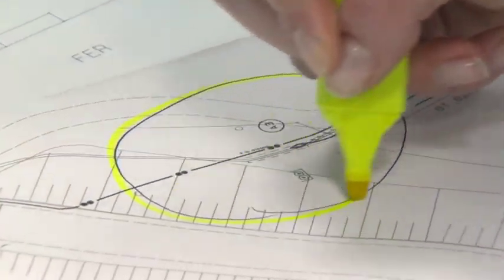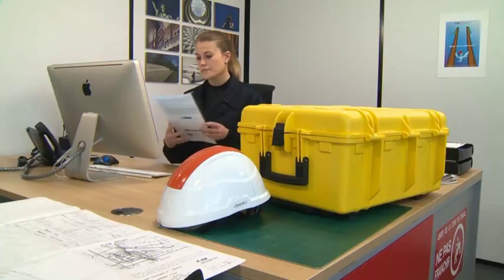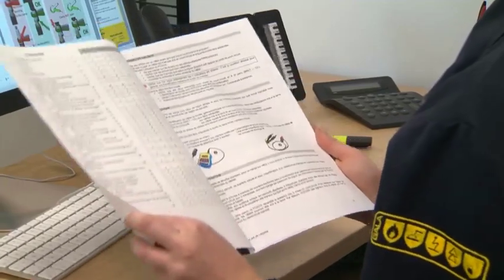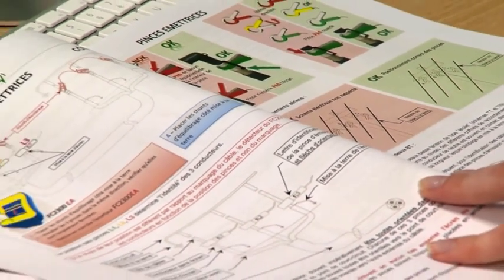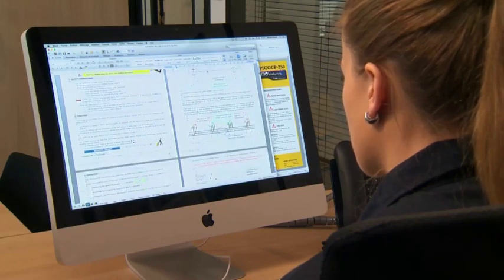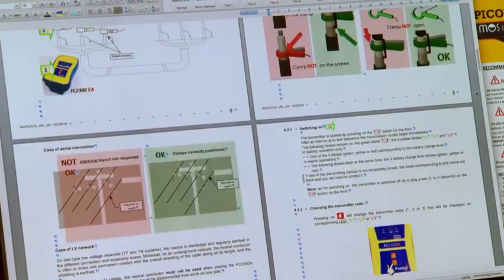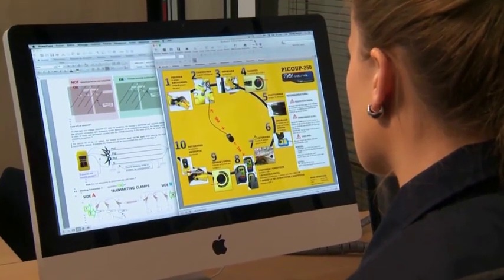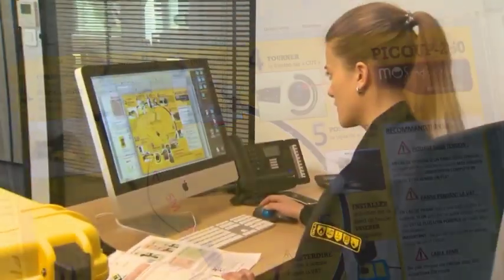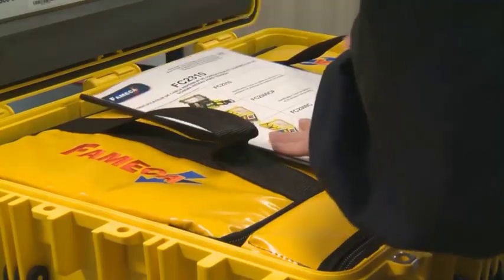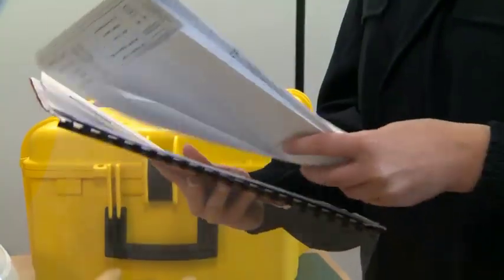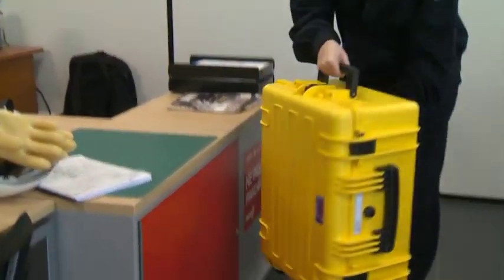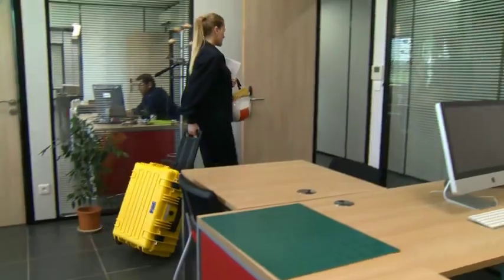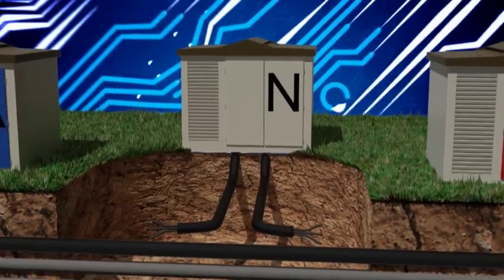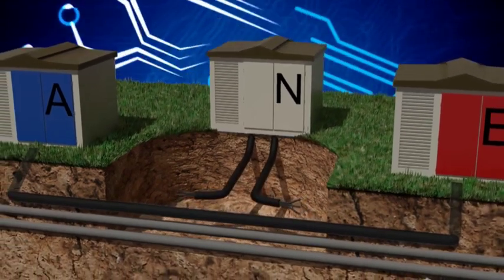When connecting a new substation, for instance, the electricians have to work within the framework of a safety procedure. This procedure is known as decommissioning or disconnection. For underground networks, cable identification on the spot is the third stage of the disconnection procedure. It requires pre-identification, use of a spiking tool, cable cutting, as well as testing for electrical continuity. This sequence is specific to underground networks and is also referred to as secure identification. Today's intervention consists in preparing the connection of a new substation.